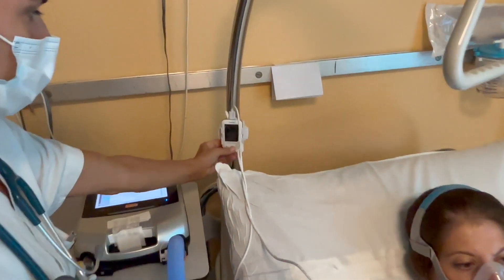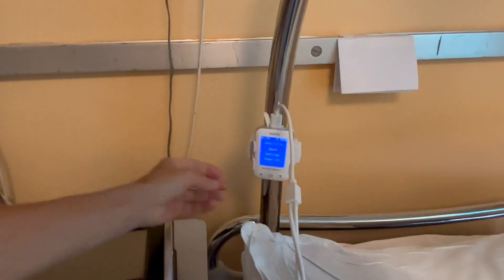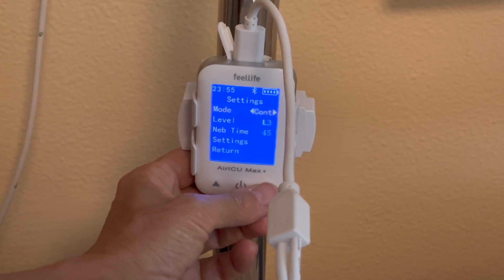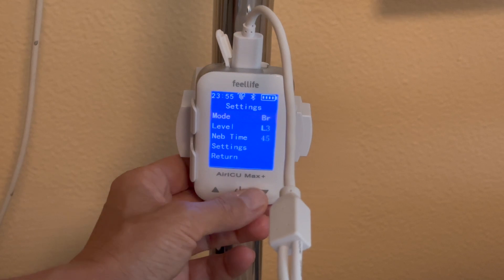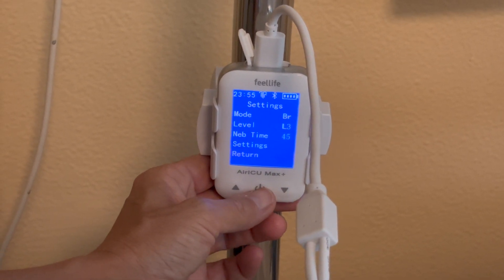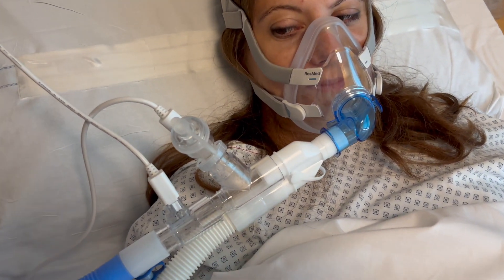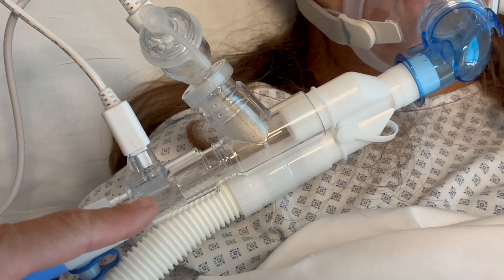I will start the AirICU Max+. I will set the mode — sensing mode — and the time, and I will start. As you can see, it is synchronized with the inspiratory time, with the inspiration of the patient.